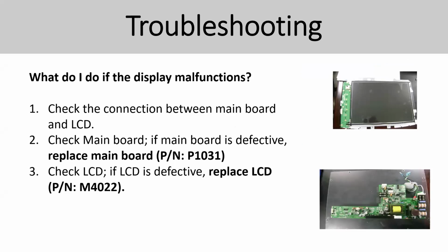LCD is one of the common problems that we can see. Normally the display is not working properly or shows a blank screen, so you need to replace the display. When you power up, it doesn't turn on, but the power is coming in. So that's another thing you need to know, how to check the LCD. When you power up, the power supply is working properly, but there is no display, but you can hear all the sounds. That means something is wrong with the display.